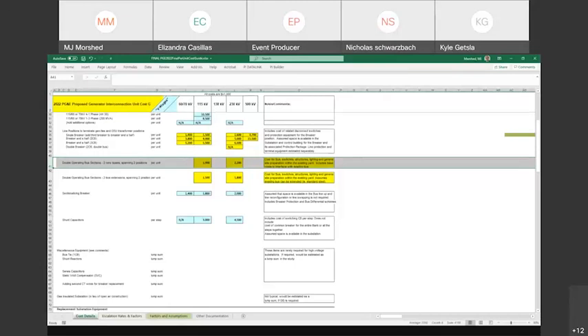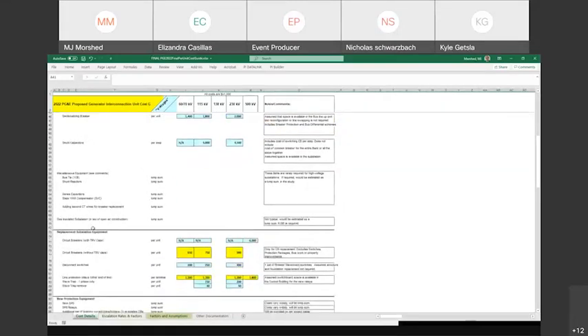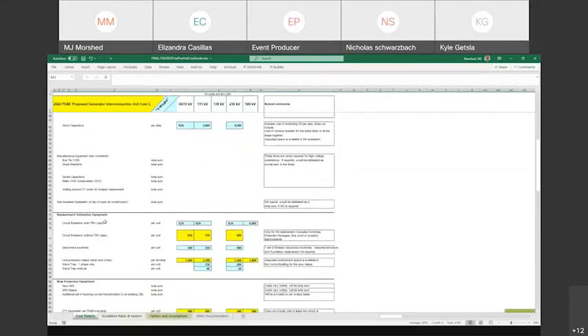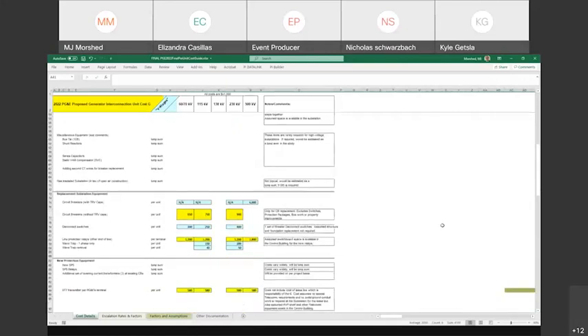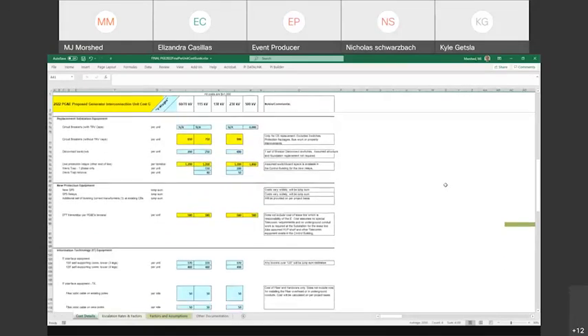The other item that increased, line protection relays, went up over 50%. These are remote terminal upgrades typically used when we have a new switching station and upgrade remote terminals. Our protection standard changed a few years back, but we're starting to realize the actuals of that. In addition to changing out line relays, we typically have to change out breaker control relays as well so they're compatible with the new relays, so those costs went up.